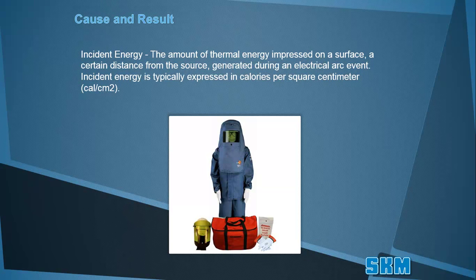According to the NFPA 70E standard, for incident energy equal to or less than 1.2 calories per centimeter squared, PPE of a long sleeve shirt and long pants or coverall, face shield, safety glasses, hearing protection, and heavy duty gloves are required. An incident energy of 1.2 calories per centimeter squared is enough to cause second degree burns.